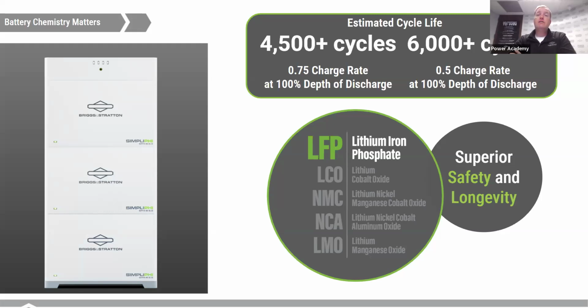You can see the 6,000 cycles, right? If you divide that by 365, that's like 16 years, but that's a C/2 discharge rate, meaning you can charge and discharge it in 2 hours. If you cycle it a little slower, and most people do, especially when the solar window is longer, you're not really discharging the battery in 2 hours, you could expect more cycles.